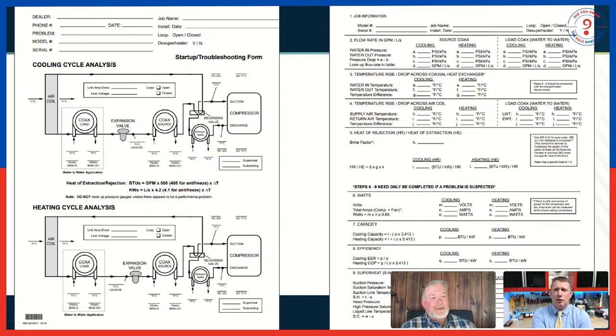You mean like dirty condenser coils? I mean, like, relatable here? Usually it's not as much dirty condenser coils as it is maybe a bad loop pump, or if it's an open loop system, it could be a number of things. Surprisingly, we don't run into that many dirty water coils, even on open loop well water systems where we're taking water out of the well and running it through the unit and discharging it. Part of the reason is we want to make sure we've got good water before we do something like that, so water tests and that sort of thing are really important there.